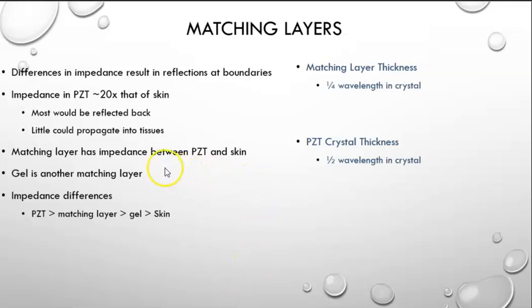So we have a matching layer, and it's always going to have an impedance somewhere between the PZT crystal and the skin. So very important, all matching layers have an impedance somewhere between the two materials that you're going to have it go between. The gel also forms a bit of a matching layer, maybe not so much as the actual matching layer, but it is also a matching layer too. So that's another purpose of the gel.